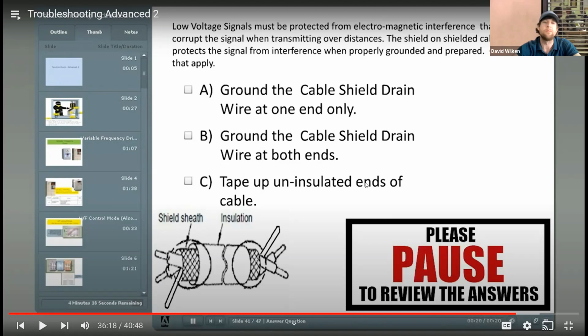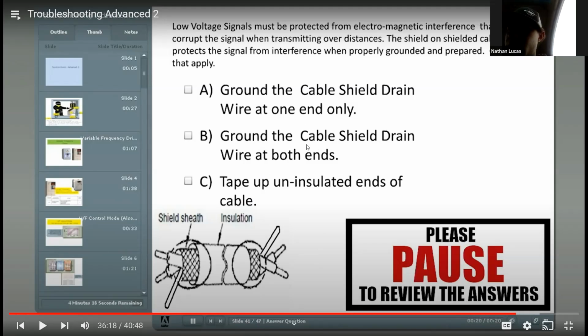Do you think you should be taping up the uninsulated ends of the cable? No, I don't feel like that would protect it. For the same reason you do want to, because that would ground it anywhere there's metal insulation around this. So that's connecting all the way through the cable. That drain wire is pulling the transients away. It's pulling in one direction. Well, for the same reason, you don't want it grounded at both ends. You don't want to have this insulation free if it's touching the cabinet or if it's touching a ground wire, anything that's grounded, now you have a ground there.